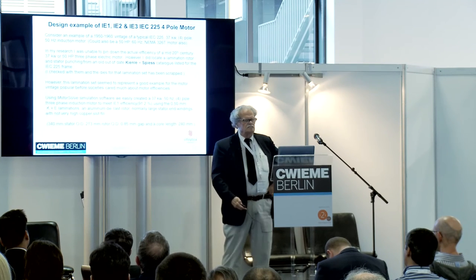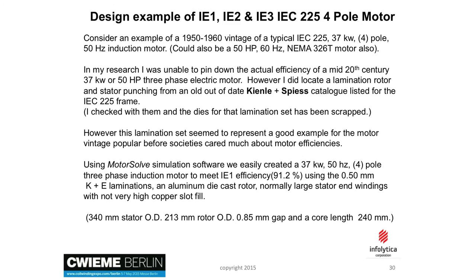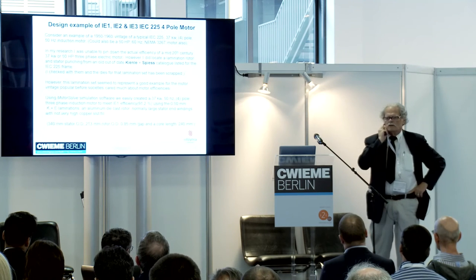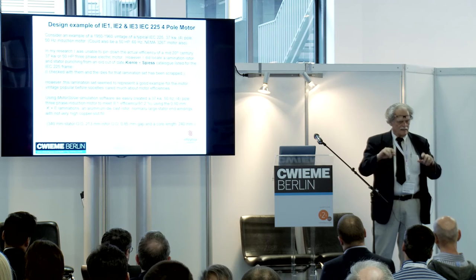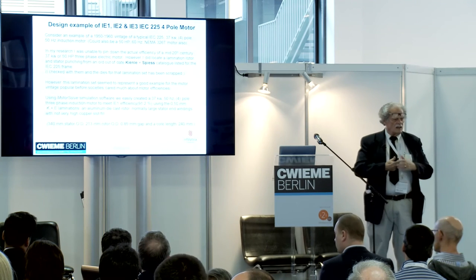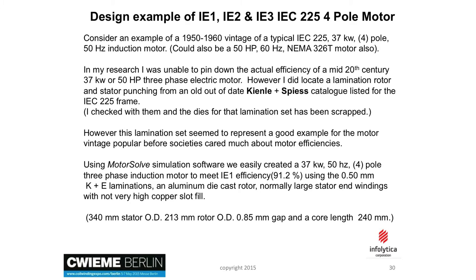So what we did, we used the motor simulation software to model that for its performance, and we used the steel loss data from the electrical steel companies, which is a problem in itself. It was found out years ago that if you use the loss data for electrical steels published by the steel companies, and you build a motor and test it, your iron losses come out much higher, and it varies with the size of the motor. The reason is that the manufacturing of the core adds losses to the finished core. If you weld the core, or cleat it, or rivet it, that adds losses. So in your simulation software, you have to put a calibration factor or a fudge factor in there based on some real measurements so that you can use that for the next one.